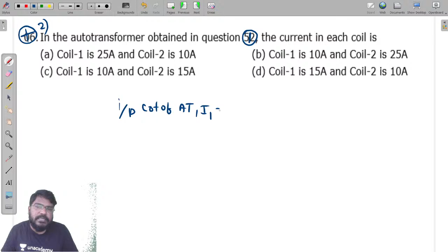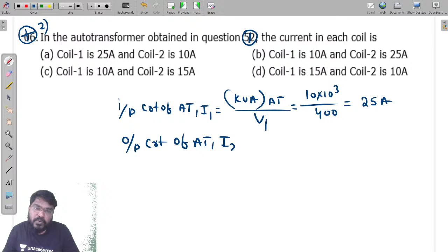The input current of the auto transformer, that is I1, is equal to the kVA rating of the auto transformer divided by V1. So it is equal to 10 into 10 to the power of 3 divided by 400 volts. So that is equal to 25 amps.